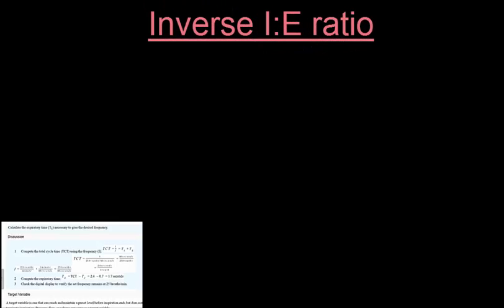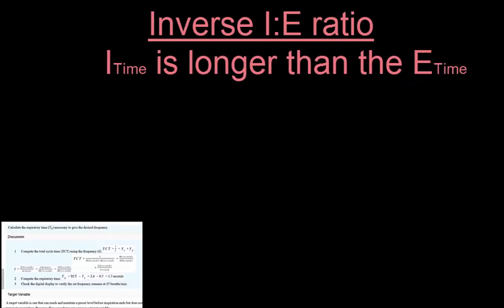Occasionally we want to inverse the IE ratio — making the inspiratory time longer than the expiratory time. This is called an inverse IE ratio, and may be designated as 2:1 or equivalently as 1:0.5.